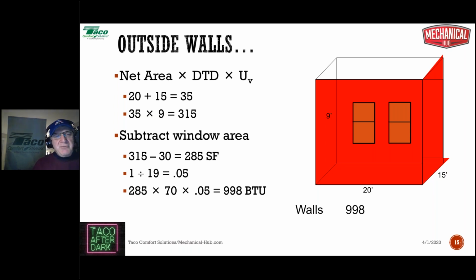So in this case, 285 square feet, our net wall area, times 70 degrees design temperature difference, times 0.05, our U value, that gives us a wall load of 998 BTUs, all right?